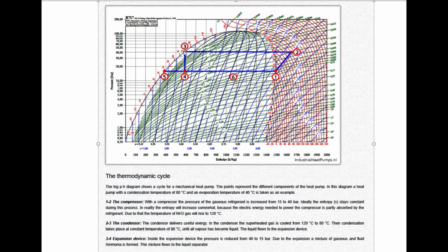So it's then put through an expansion valve, and because there's no work done on it, the energy in it has to be the same. So you arrive back at this point here, which is a bit of liquid, and then you add more energy to it and bring it back up to there. This here is pumped back up to this point over here because it's a liquid. So you've now completed the cycle, and you've taken the heat out up here and rejected it down here.